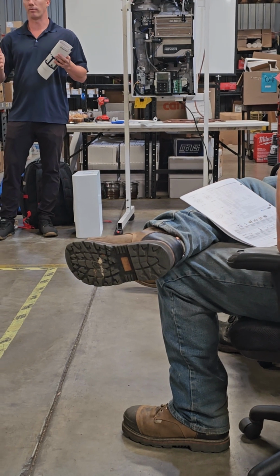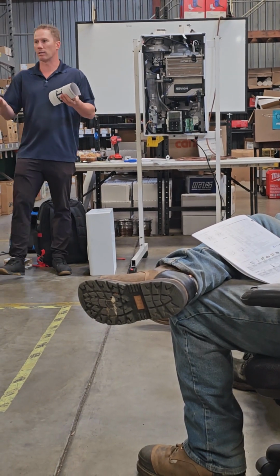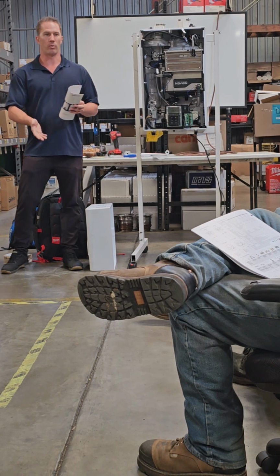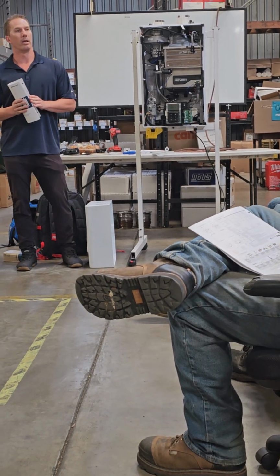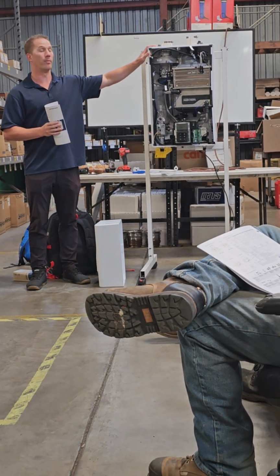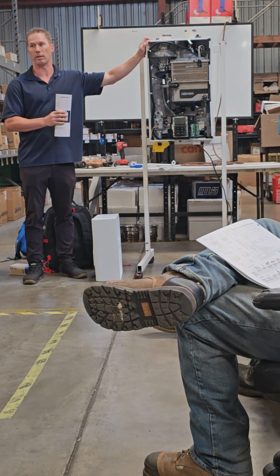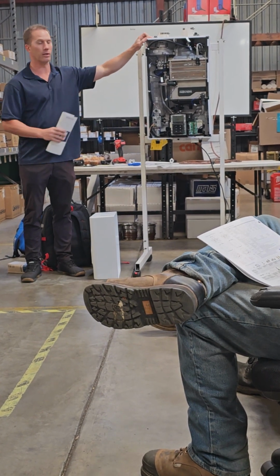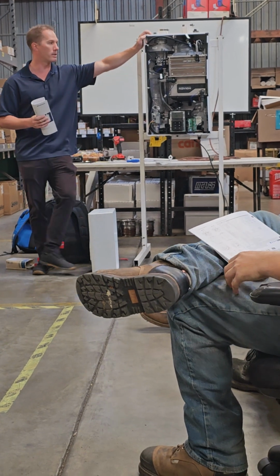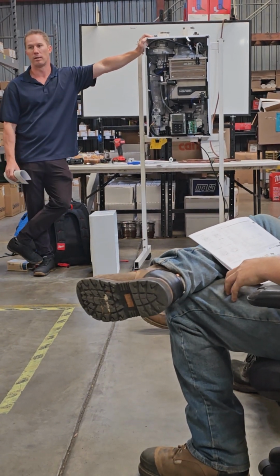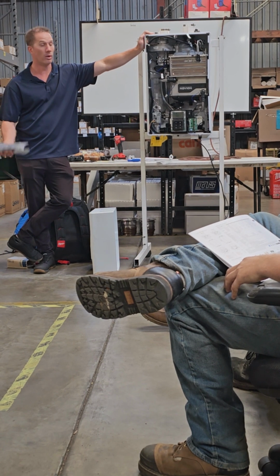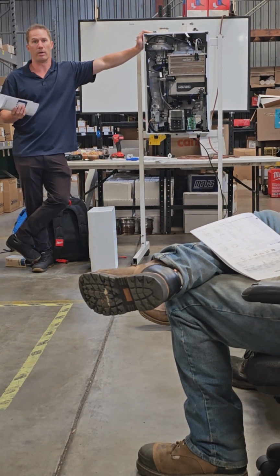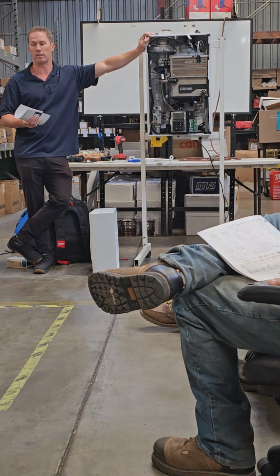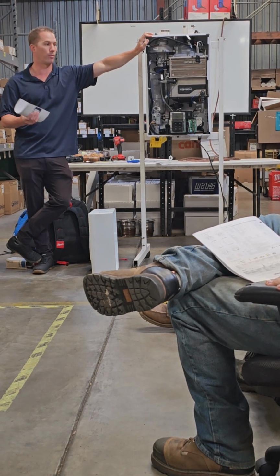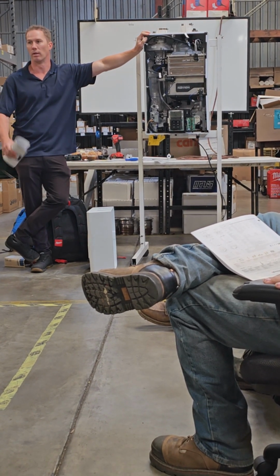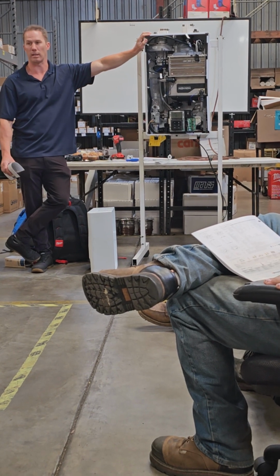So they only brought it down 1.5. I was like, yeah, you're technically softening the water, but they put in the wrong system there. This unit needs a maximum of 12 grains of hardness to still be good and not eat through heat exchangers. If you're up to 20 grains of hardness, it's going to eat through a heat exchanger in like 8 months. So the water was being softened, but it was the wrong whole-house water softening system, and it was only bringing it down 1.5 grains of hardness - still way too hard, so it just kept eating through heat exchangers.